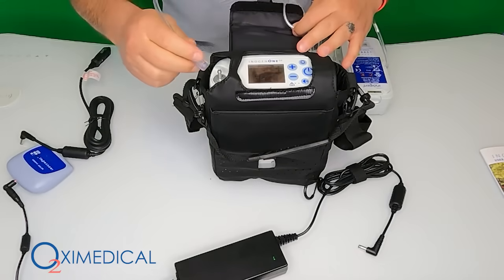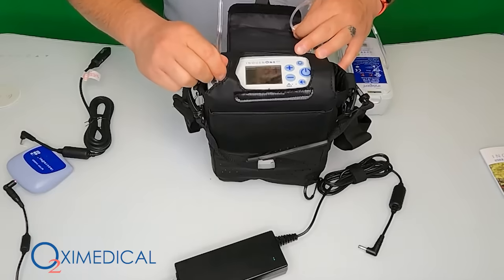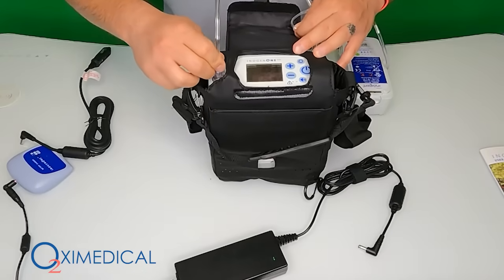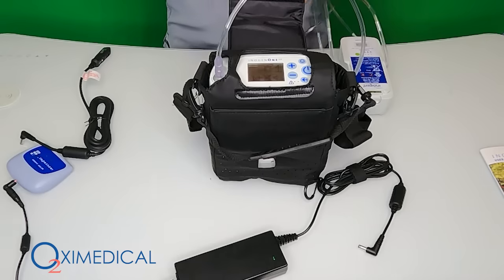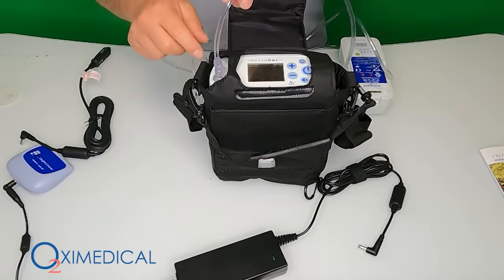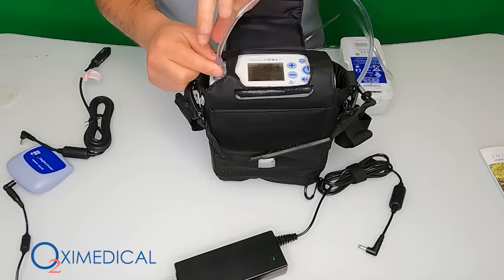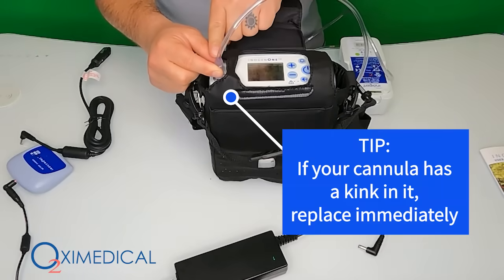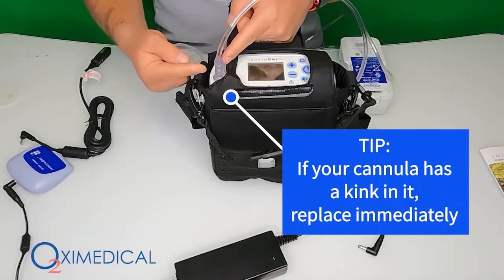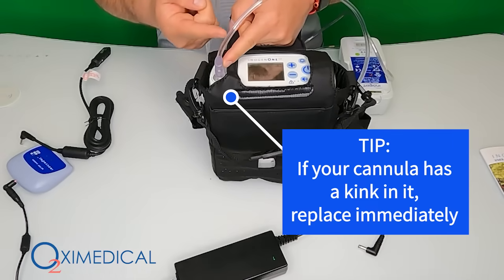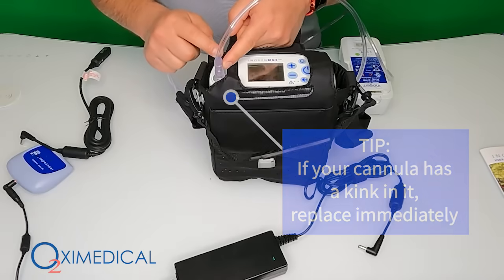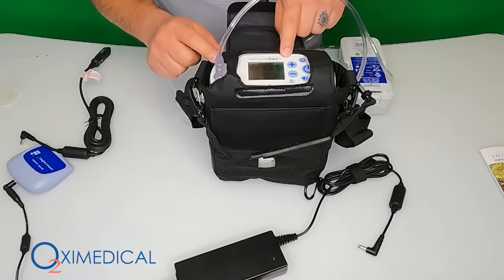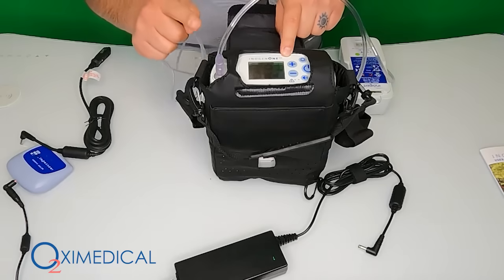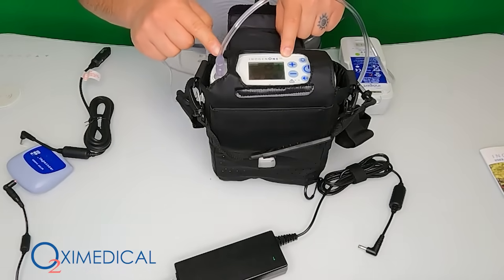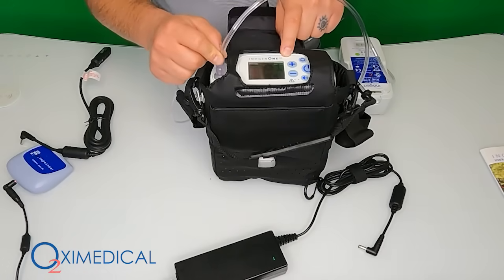A new cannula, you're going to want to gently slide in on top of the cannula with a nice clean connection. Things to look for when you know your cannula gets old. This piece right here will kink, and it can actually cut off the clean connection of the machine delivering oxygen through the cannula. Sometimes it could set off an alarm on your concentrator. Always check your cannula to make sure it's not kinked. If it's kinked or if it's really bendy, that's time to replace your cannula, usually once a month.